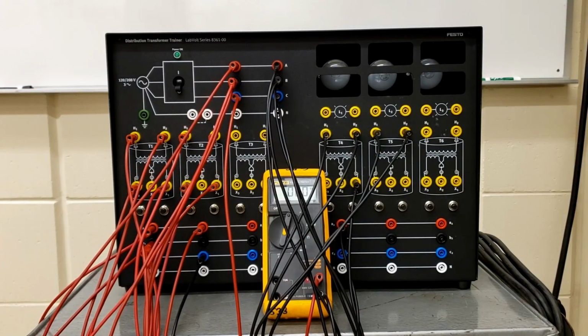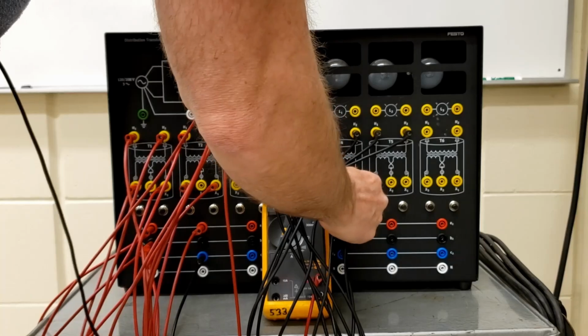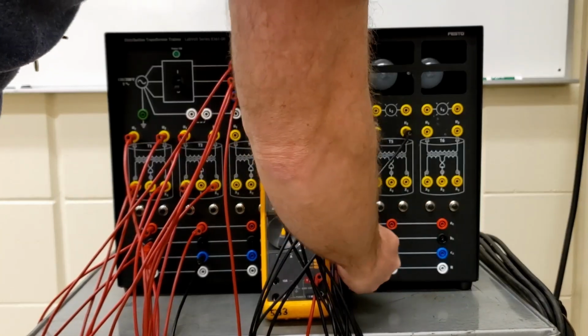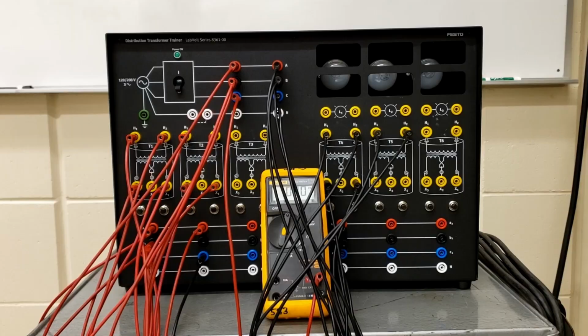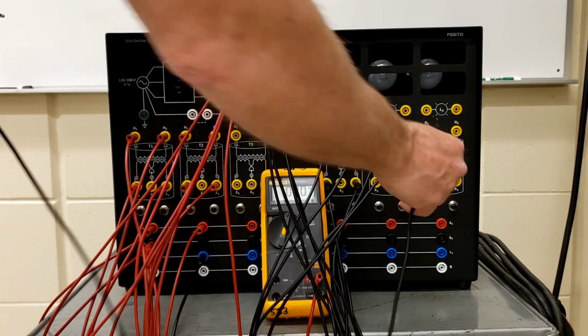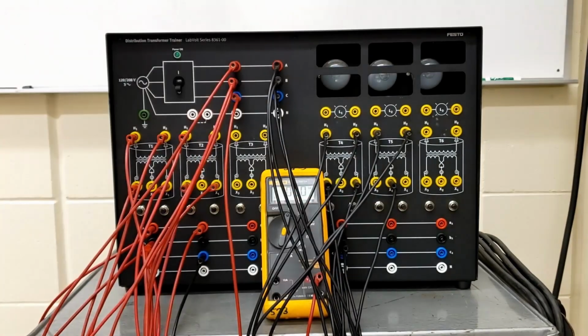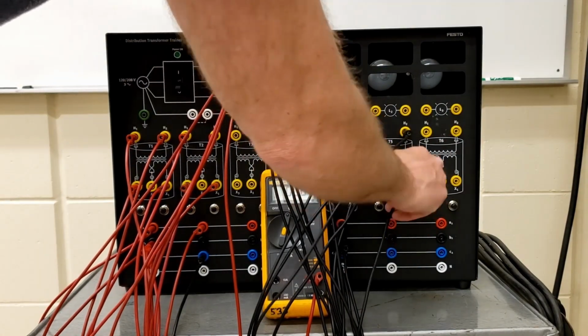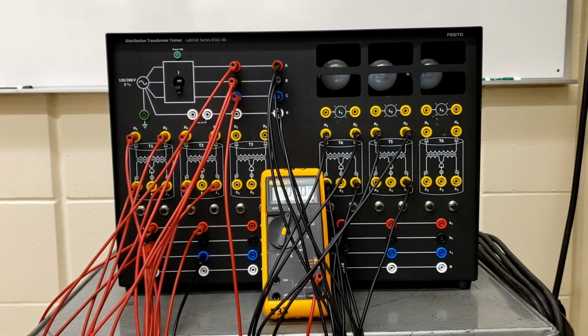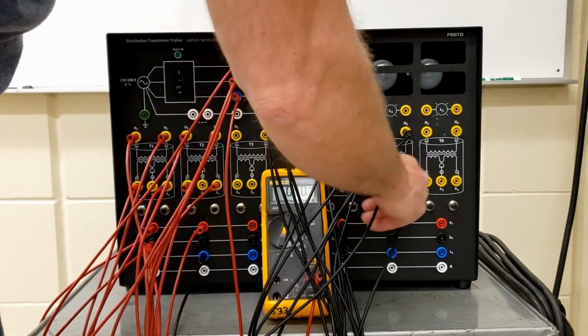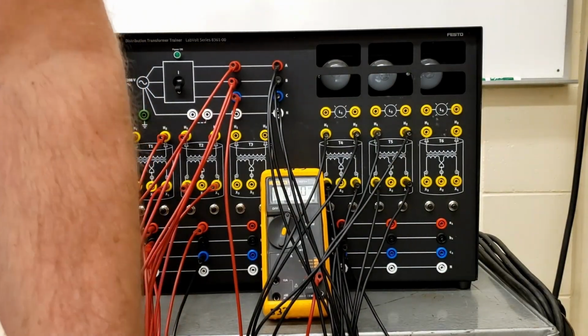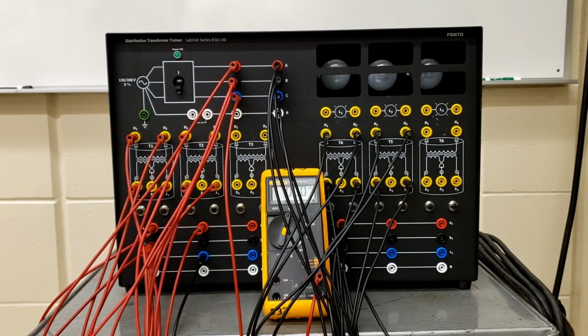Then we have X3 feeding B, so A to B, and then this guy should be B to C, so X1 of transformer 2 goes to B. Okay, looks good. And then, wait a minute, X1 of transformer 2, okay, and X3 goes to C. Excellent. Okay, so now we've paralleled the two open deltas, and we're going to look at the voltage between A1 and A2. So we're going to look at the voltage between those 2 points.